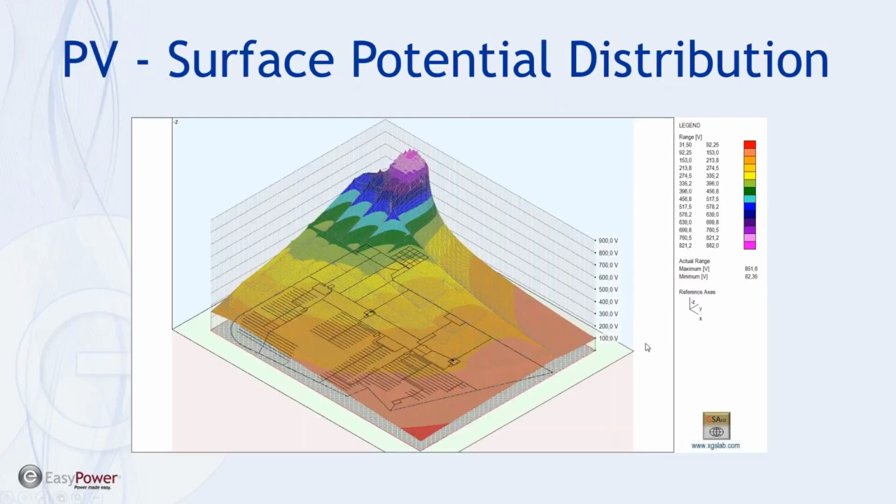What that looks like on our elevation chart now is essentially showing the same thing as the last one, but in an easier visual way to look at. You can see that the substation grid has been raised up to a very high level, and everything else that's still connected has been raised up, but not to that same extent.